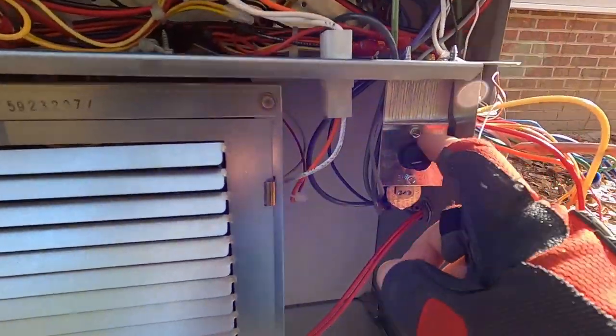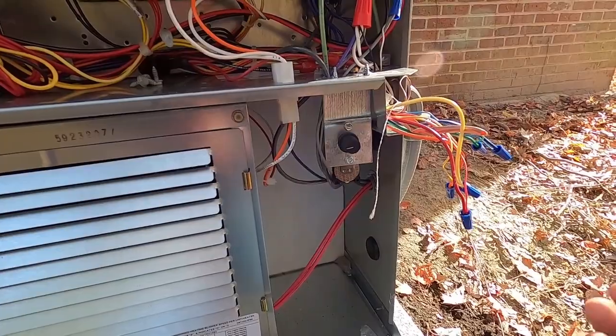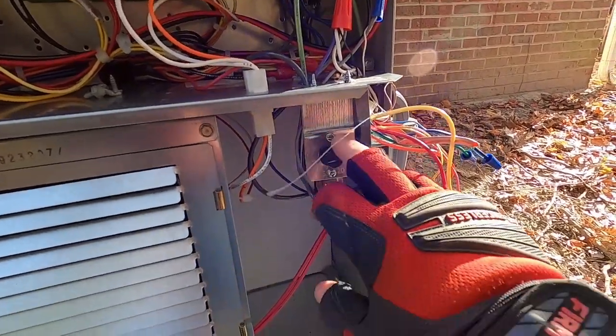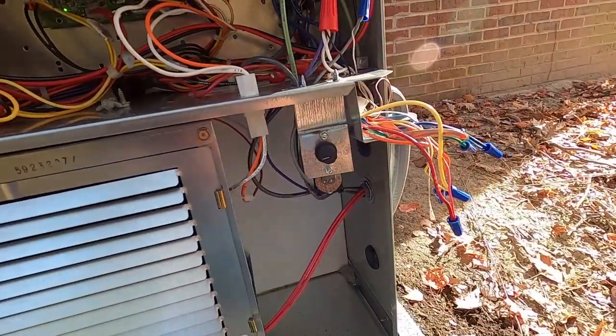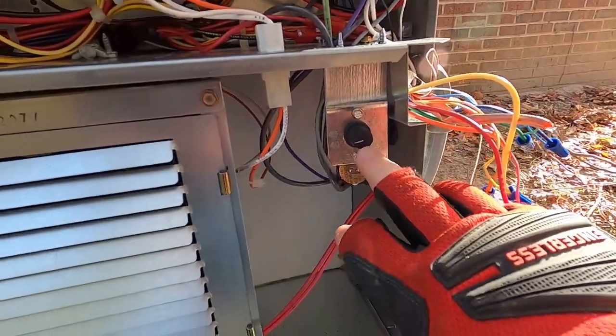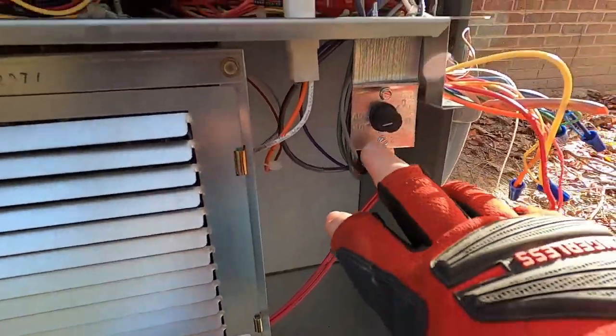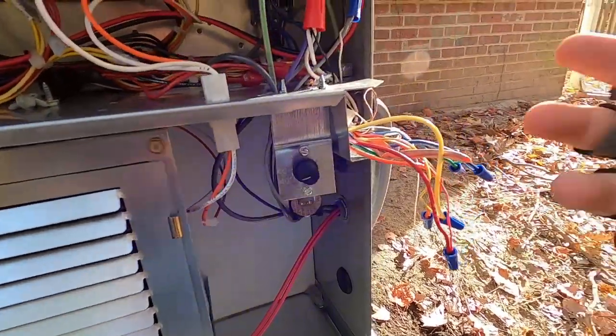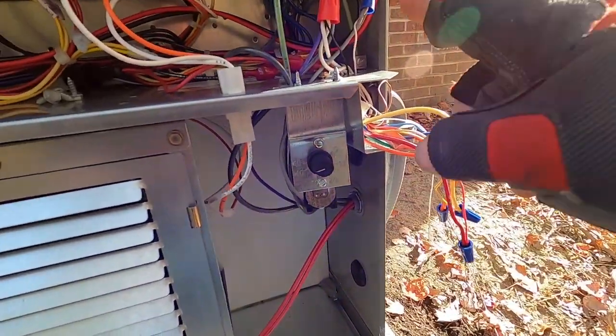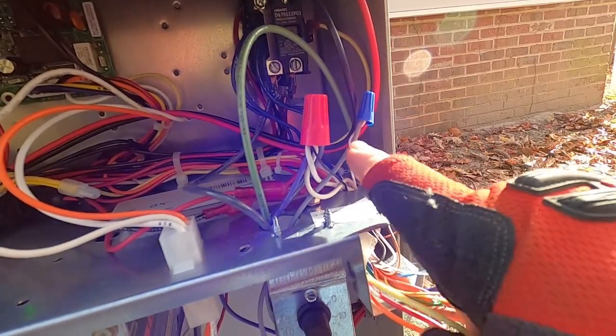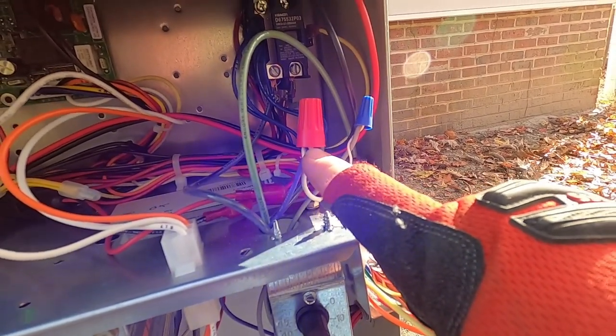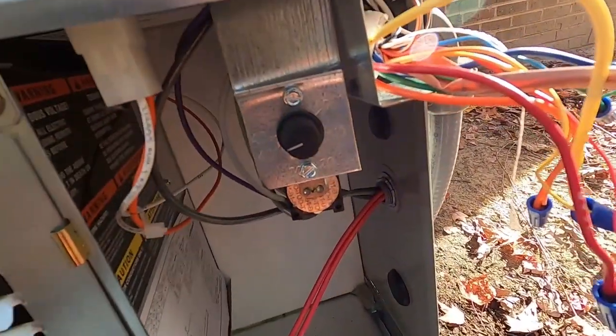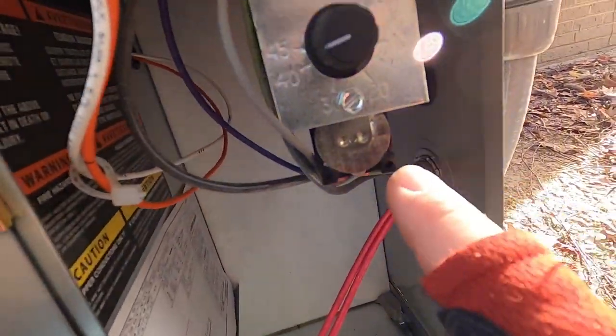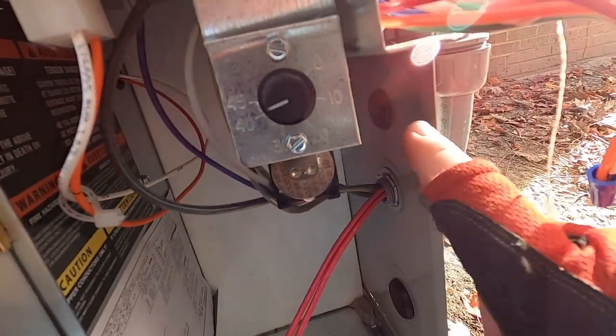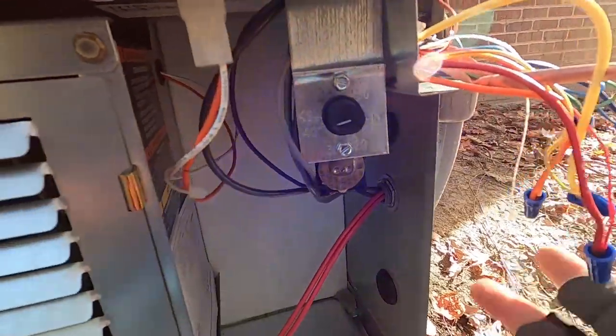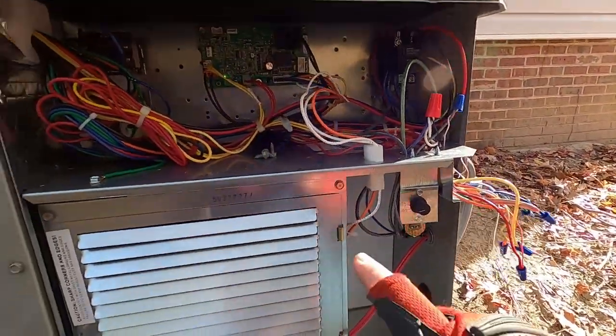What I was explaining to you about this, in some situations we'll put a wired outdoor temperature sensor in. Sometimes we just use these mechanical outdoor switches to lock out the heat strips below or above a certain temperature. So we'll set it at 40. It's open above 40. Temperature drops below 40, it closes. If the thermostat's calling for auxiliary, when that switch closes, it makes over here to the heat strips, turns them on. But with this particular version of this switch, it's got this little disc in here. It doesn't have the thermocouple that goes out to the exterior of the unit, so it's not reading a true outdoor temperature.